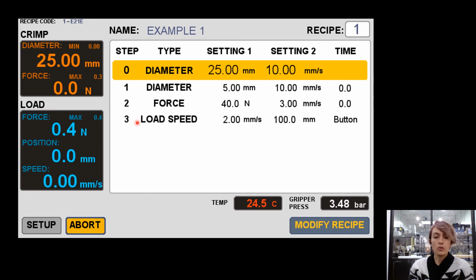The third step I've programmed is just a load speed step. This loading step is what initiates the auto pushrod loader to start moving forward. It also initiates the power feed if you have the power feed option. And I'm simply telling the machine that I wanted to move at 2 millimeters per second because, again, I'm controlling the speed. And I wanted to move for a distance of 100 millimeters.